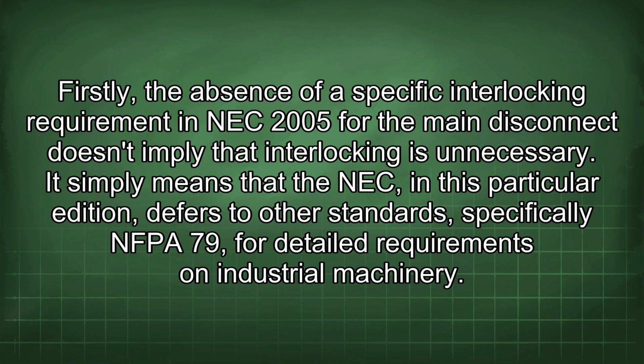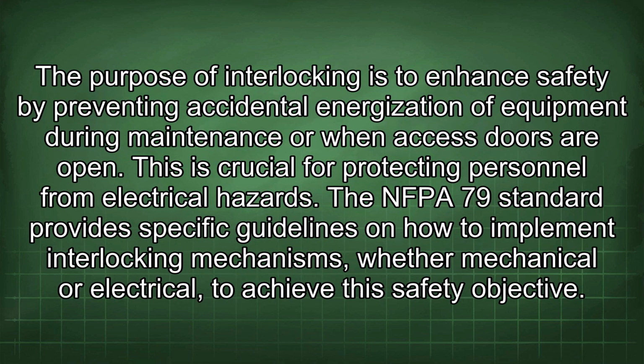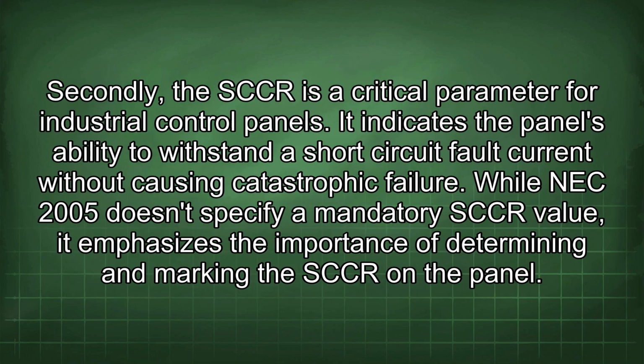Firstly, the absence of a specific interlocking requirement in NEC 2005 for the main disconnect doesn't imply that interlocking is unnecessary. It simply means that the NEC, in this particular edition, defers to other standards, specifically NFPA 79, for detailed requirements on industrial machinery. The purpose of interlocking is to enhance safety by preventing accidental energization of equipment during maintenance or when access doors are open. This is crucial for protecting personnel from electrical hazards. The NFPA 79 standard provides specific guidelines on how to implement interlocking mechanisms, whether mechanical or electrical, to achieve the safety objective.